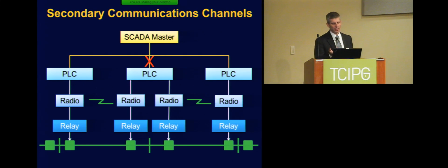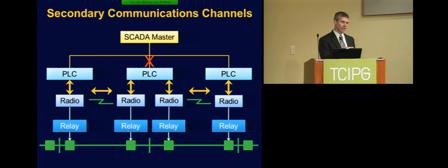Instead of sending the data up through the PLC, I can take advantage of the bandwidth available in those radios and transmit the SCADA data over to the adjacent substation, then map that up through the PLC. So in this case, I'd go from the radio on the left-hand side in the middle substation over to the left-hand side radio, up through the PLC and up to the SCADA master.